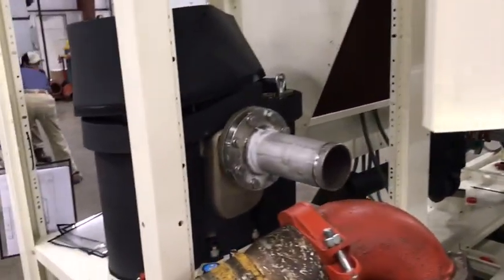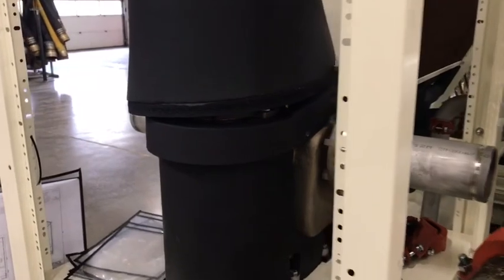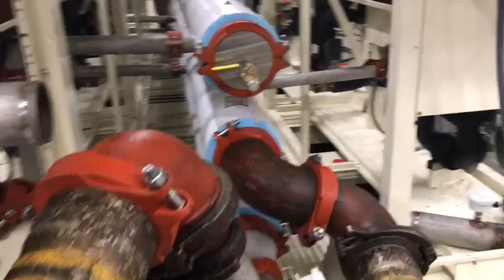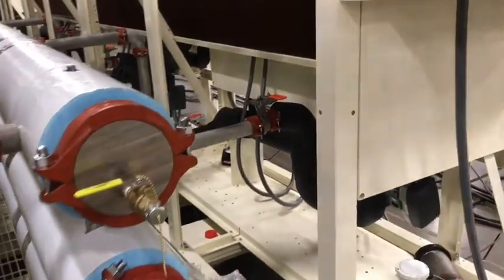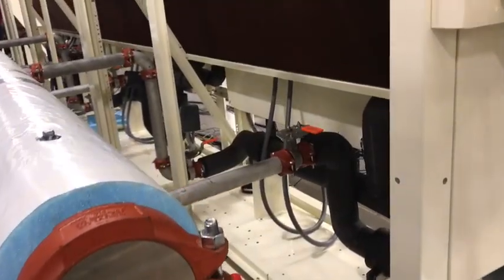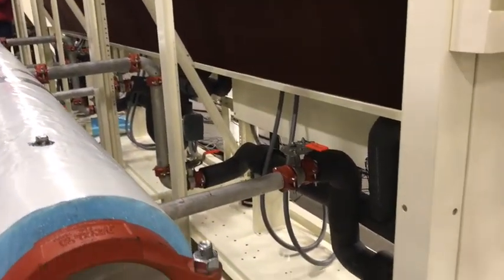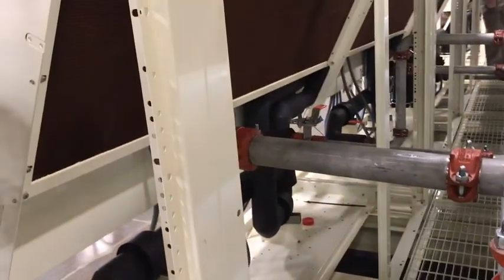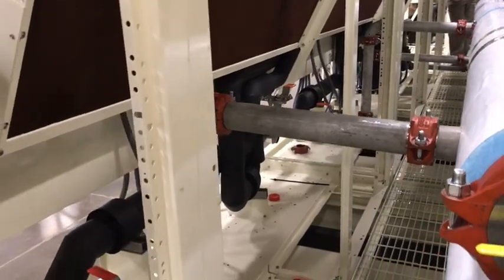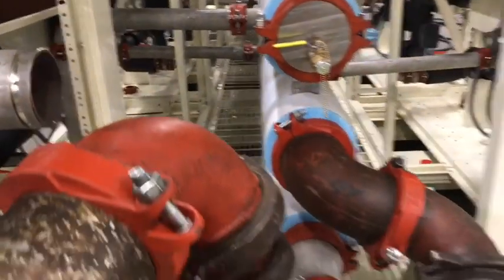And then we'll get a view of the dual basket strainer, and then the headers in the free cooling sections. We'll talk about the 3 headers in just a little bit. So a view into the free cooling module in the back, you can see the 3-way valve that opens when the air temperature is sufficiently cold to do free cooling.